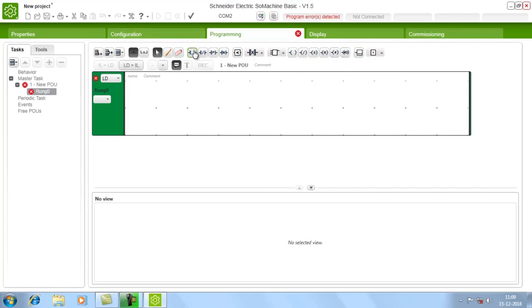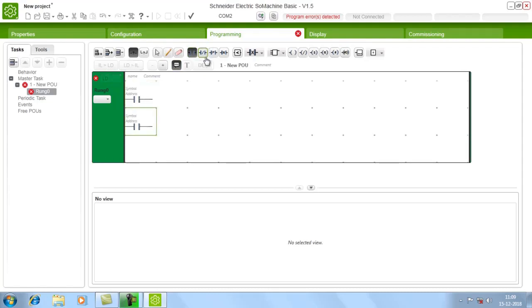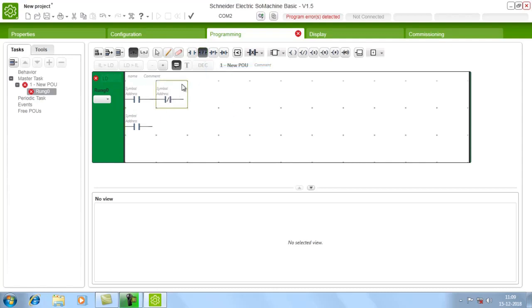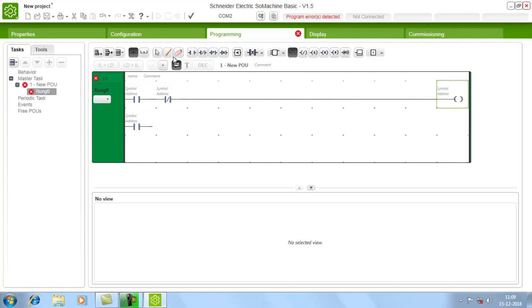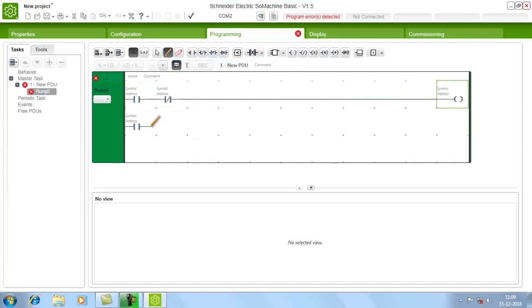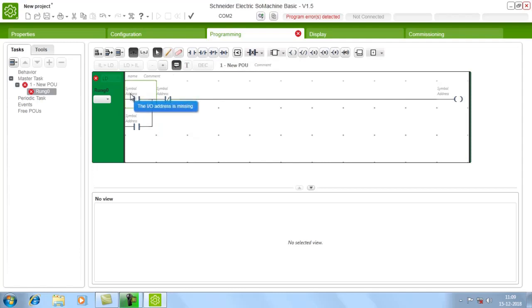Now let us see a basic DOL starter program. I need a NO contact, so choose NO and place it in the rung. Then choose one NC contact and place it here. Then add one coil. Then choose the pencil and draw the vertical line for latching. You will see two options: Symbol and Address — click Address.